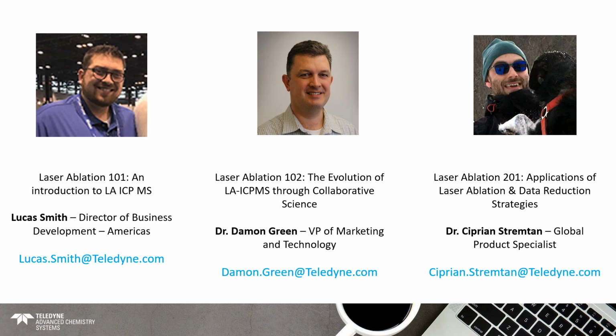All right, another question. What is the relationship between HDIP and Chromium? Can HDIP be used with other laser systems other than Iridia? The short answer is yes, HDIP can be used with all the laser ablation systems manufactured by CETAC or Photon Machines. I'm talking about 213 lasers, excimer lasers, the entire range, so Excite, Excite Plus, HE, and Iridia as well.